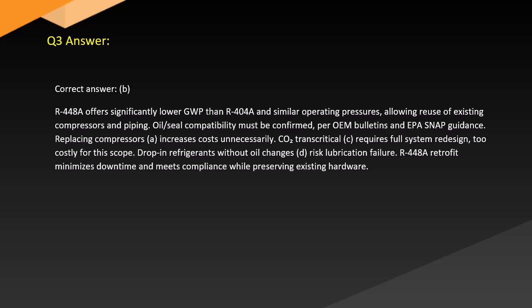Answer. Correct answer: B. R448A offers significantly lower GWP than R404A and similar operating pressures, allowing reuse of existing compressors and piping. Oil and seal compatibility must be confirmed per OEM bulletins and EPA SNAP guidance. Replacing compressors (A) increases costs unnecessarily. CO2 transcritical (C) requires full system redesign, too costly for this scope. Drop-in refrigerants without oil changes (D) risk lubrication failure. R448A retrofit minimizes downtime and meets compliance while preserving existing hardware.